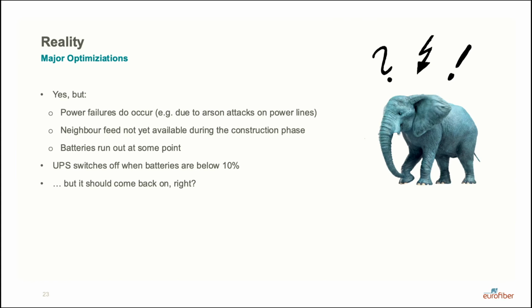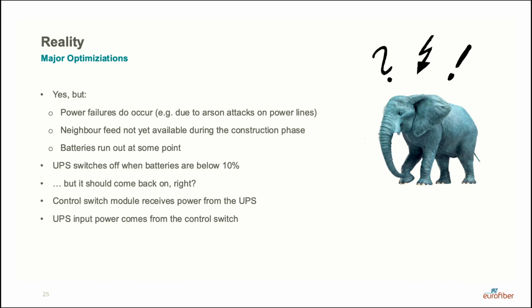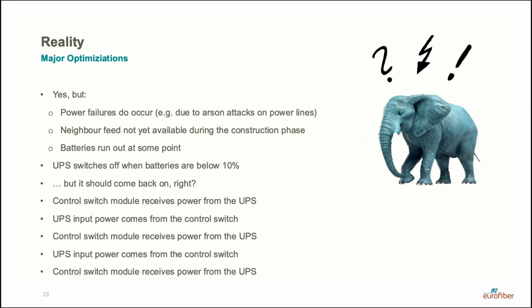Well, that's when we noticed that control switch needs power coming in from the UPS, but the UPS has switched off because the batteries are below 10%, to protect them. And the UPS is not coming back on because it would need power from the control switch, and the control switch needs power from the UPS. So we basically noticed a cyclic dependency in our power design, which meant the cabinets were not cold-start capable, a design flaw we had to fix later on.